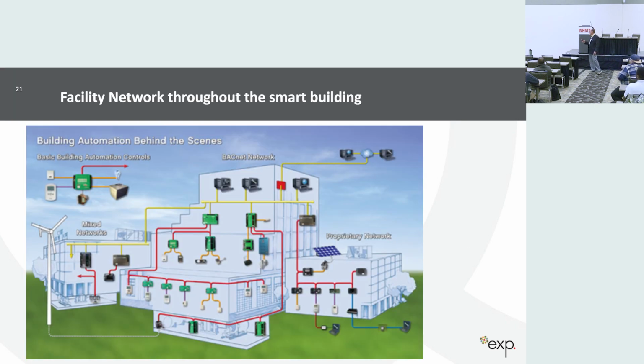This is a diagram showing different systems within a building, and the different colors represent different types of networks. You can have a typical N2 network, then a BACnet network, you can have a Modbus network that might go to the PV panels or the electrical system. But all of those things need to be interconnected. If you design the building and the network correctly, you can tie all these things together seamlessly, and you don't end up with 5 different networks in your building. Because typically what happens is a contractor just puts in a lighting control system, a BAS system, and an energy metering system separately. You want all those things to work together, and you'll save a lot of money if you do it that way.